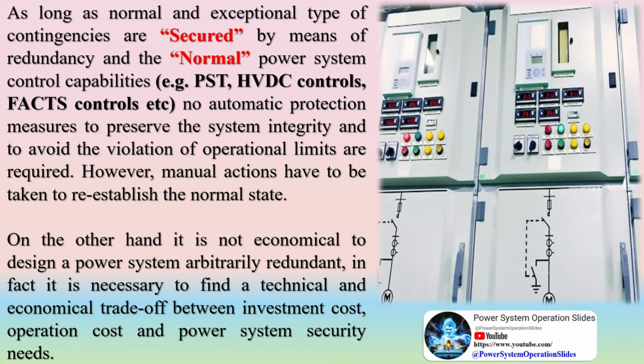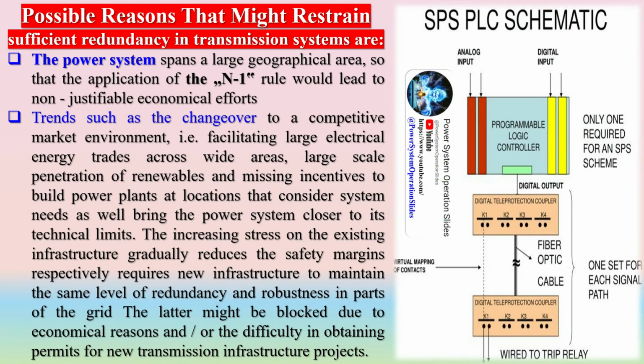To contain normal type of contingencies, the so-called N-1 rule is common practice in most large power systems worldwide. This concept is characterized by a predefined redundancy of power system elements, which ensures a sufficient safety margin and robustness to operate the power system. Given that the transmission system loading is moderate, also exceptional type of contingencies can often be handled due to this robustness. As long as normal and exceptional type of contingencies are secured by means of redundancy and the normal power system control capabilities, e.g. PST, HVDC controls, FACTS controls, etc., no automatic protection measures to preserve the system integrity and to avoid the violation of operational limits are required. However, manual actions have to be taken to re-establish the normal state.